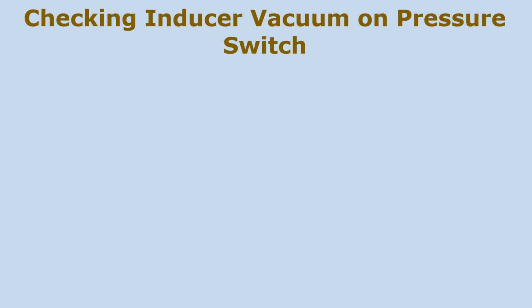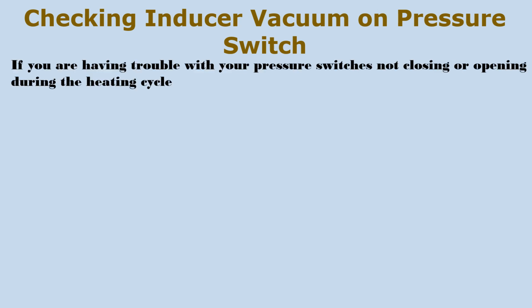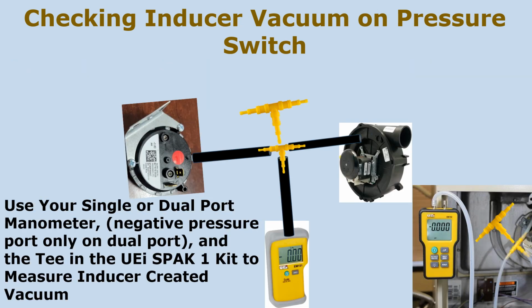Checking inducer vacuum on pressure switch. If you are having trouble with your pressure switches not closing or opening during the heating cycle, use your single or dual port manometer, negative pressure only on the dual port, and the T in the UEi SPAK1 kit to measure inducer created vacuum. And as you can see, this is how we would hook this up. That little T is very helpful with that.